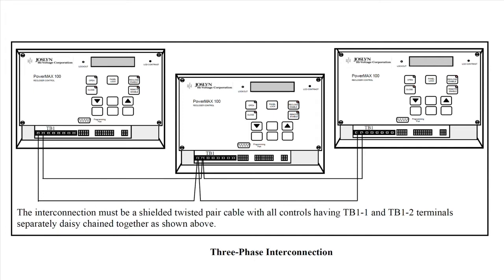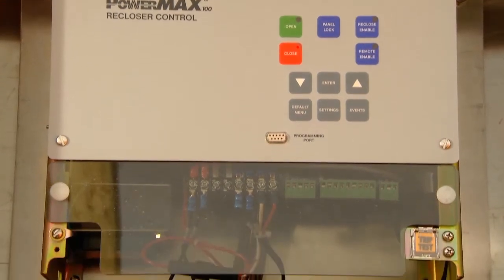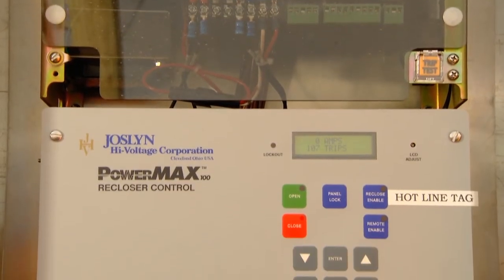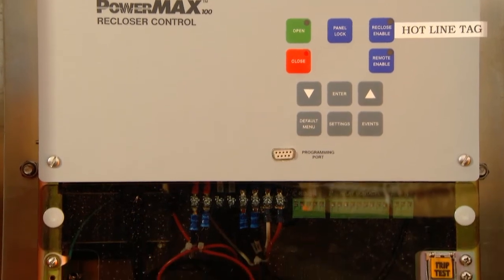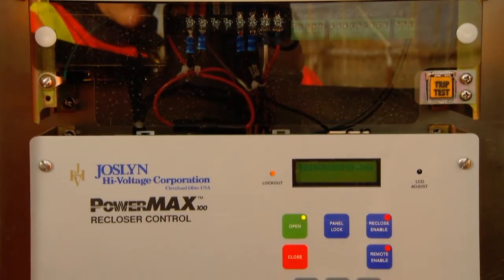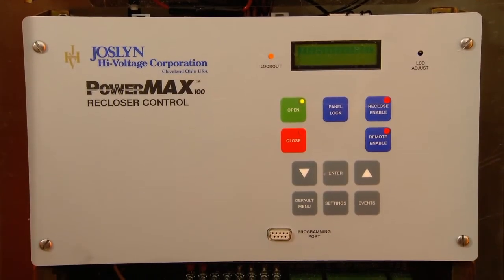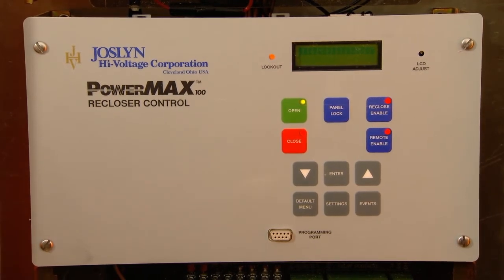Only the faulted phase or phases will have lockout indication. The other controls that were commanded to open via the three-phase lockout will only show open indication. Therefore, the faulted feeder can easily be identified. When PowerMax controls are connected together and the manual trip to lockout feature is on, manual opening of one tri-mod, whether by the open push button in the control or by the manual operating handle on the tri-mod, will result in all connected PowerMax controls opening their respective tri-mod.